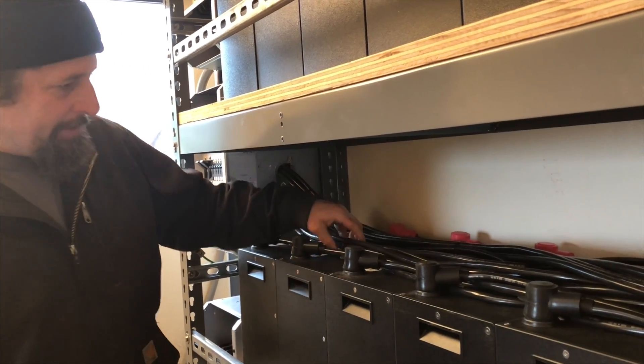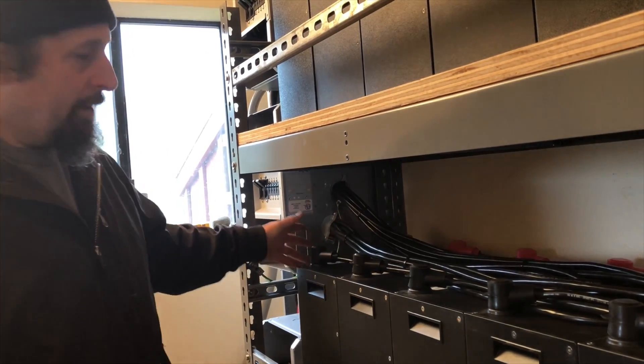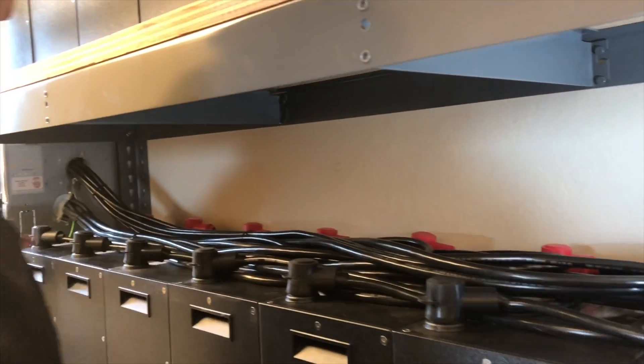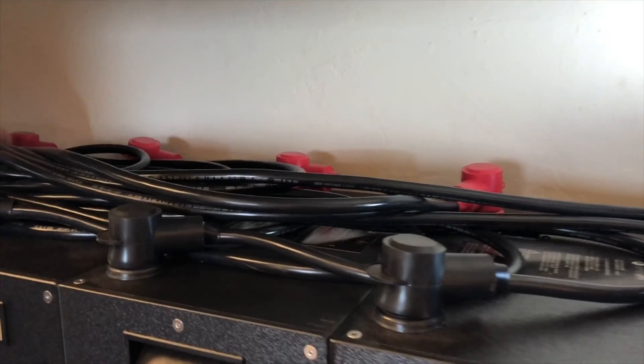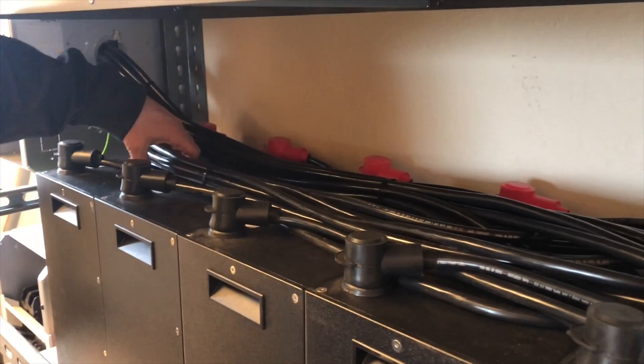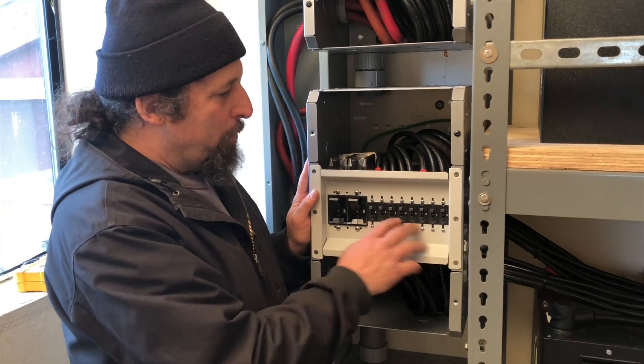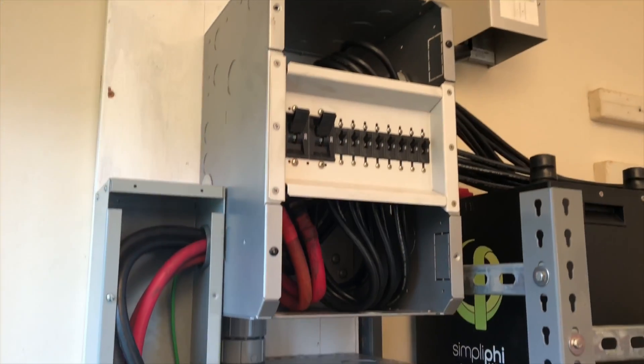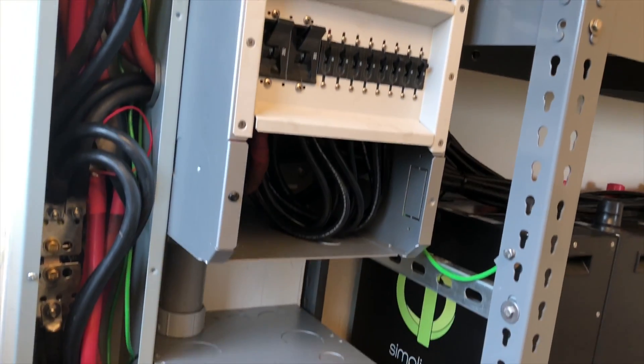As we're wiring all these batteries, since they each need to have their own circuit, it's also important to make it so that the cable links are all the same length. The farthest battery has the same cable length as the nearest battery, so we kind of had to create some loops here. There's a lot of cable to deal with, but the importance of having them all get the same charge voltage and the same amount of resistance to each battery is worth it. Each of the batteries gets an individual breaker and they're all running in parallel. If there is ever a problem with any one battery, it can shut off and you can have all the rest of the system working.